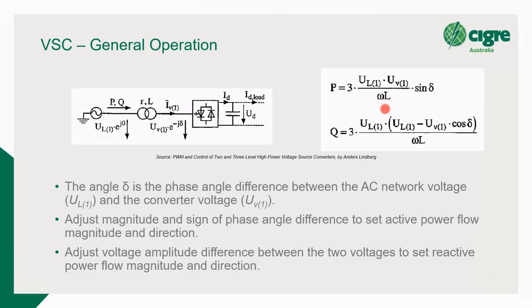These are the two formulas. They're the VSC formulas. Basically, there's a power formula and a reactive power formula. It's based on the concept that there's an AC voltage created here at the converter terminal, and there's an AC voltage on the network side, right? And there's a large inductance in between. So these formulas say that obviously the inductance is a factor, but effectively, if you can change the phase angle, you can cause power to flow in or out of the converter, and the magnitude of that. And the same goes with the amplitude. So if you look at this reactive power formula here, by adjusting the amplitude of this voltage waveform that you're creating, you can cause reactive power to flow in and out of your converter.